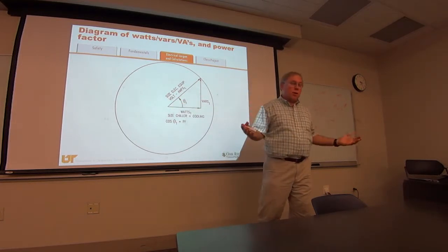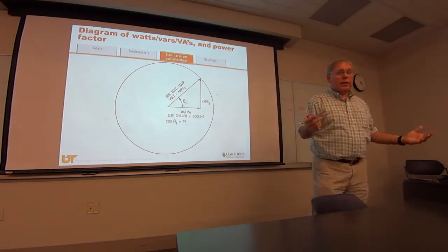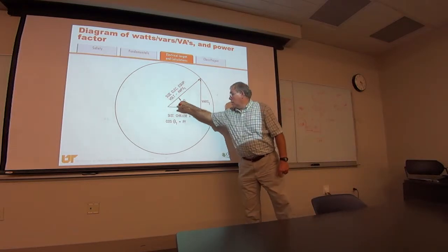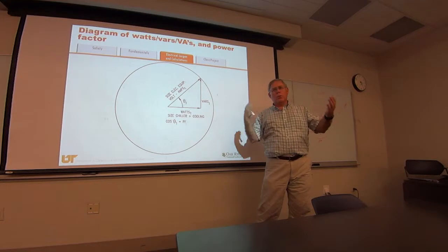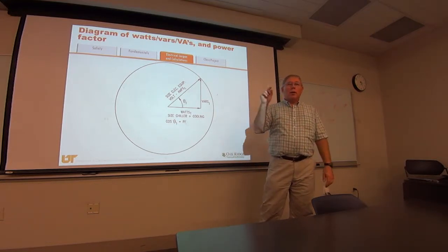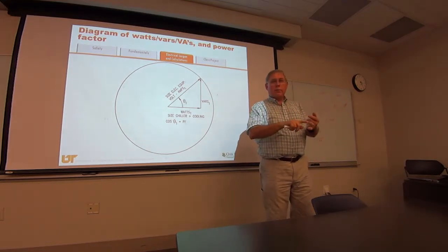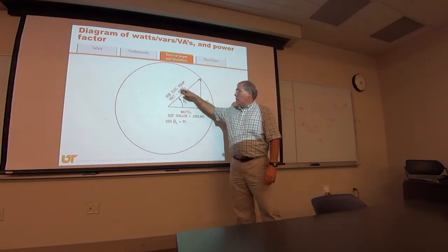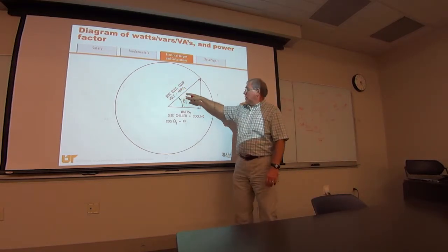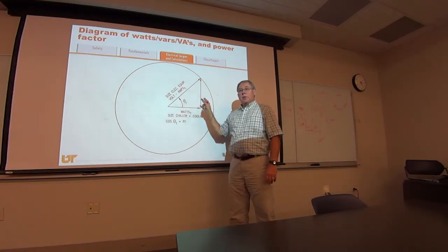Your great big computers, Titan for instance, has like a 0.99 power factor. So this angle right here is just very, very slight. I don't even make a difference between kVA and kW. But a lot of servers and things like that, they'll get 95, 93% power factor. And you've got to be careful, because if you don't, you may overload your electrical equipment, because it's looking at volt amps rather than kW.